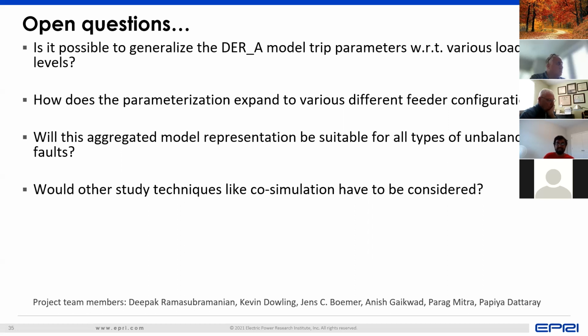The events that we study for, the events that we plan for, especially for frequency, we usually plan for largest generation loss, which used to be the single largest generator that trips. We plan for having enough reserve to cater to that single largest generation trip. But now, if a large amount of DER is going to trip because of a voltage event, characterizing the amount of DER that would trip, and understanding if that will be larger than the single largest generator, is going to be a real challenge for us to overcome, because that will play a role in understanding how much reserves we keep on the system.